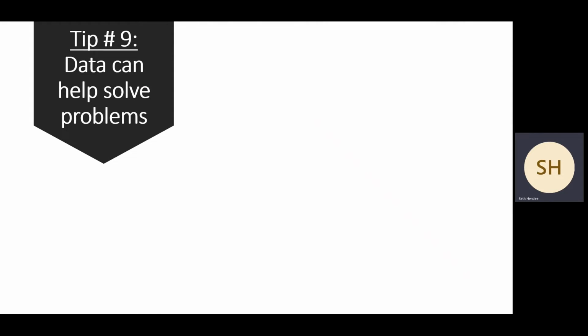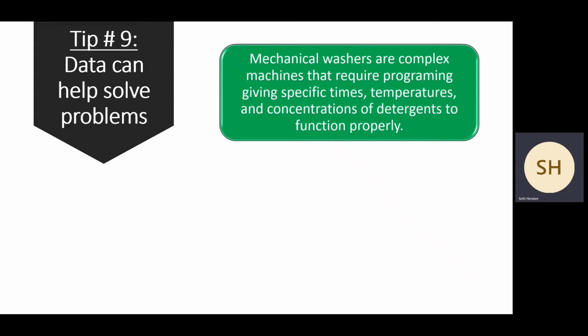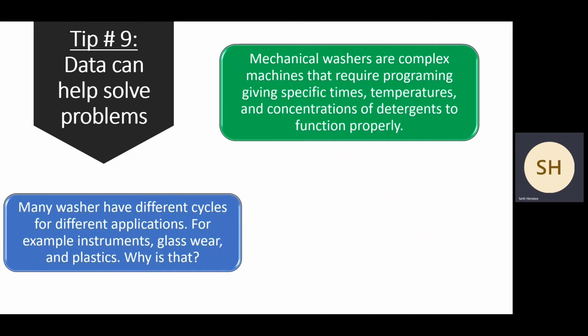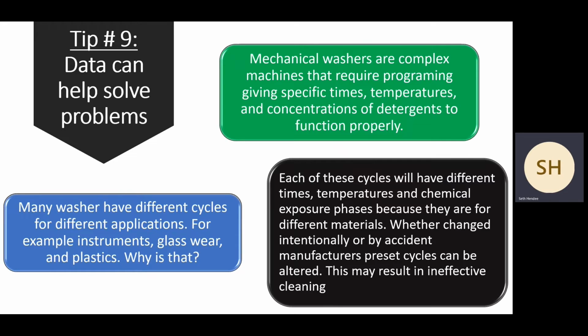Okay, tip number 9, data can help solve problems. Sometimes I know we don't love to collect data for things, but it can. Mechanical washers are complex machines that require programming, giving specific times, temperatures, and concentrations of detergent to know that they're properly functioning. Many washers have different cycles for different applications. For example, instruments, glassware, plastics. So why is that? Well, each cycle has different sets of times, temps, and chemical exposures because they are for different materials. So whether changed intentionally or accidentally, manufacturers' preset cycles can be altered.